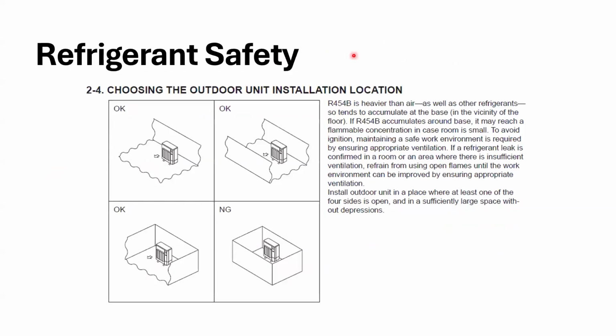This was also in there. So choosing the outdoor unit location. R454B is heavier than air, as well as other refrigerants, so tends to accumulate at the base. R454B accumulates around the base. It may reach flammability concentration in case the room is small. To avoid ignition, maintain a safe working environment.